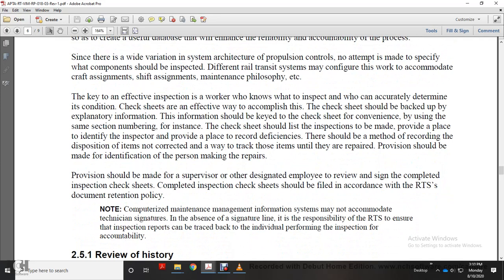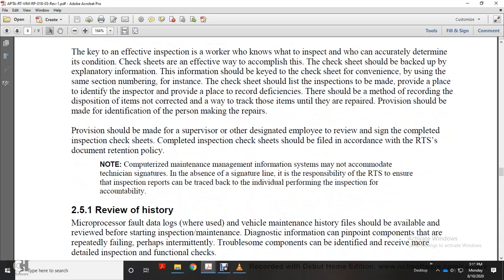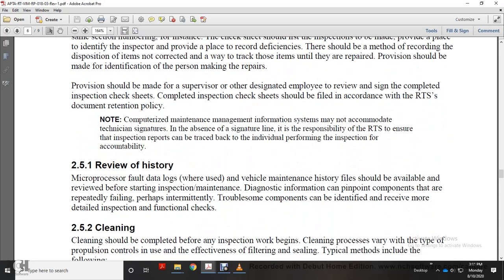The check sheet should be backed up with explanatory information. For convenience, this information should use the same section numbering as the check sheet. The check sheet should list the inspections made, with a place for the identified inspector. There should be a place to record deficiencies, recording the disposition of items not required corrected, and a way to track the items until they are repaired. Provision should be made for identification of the person making the repairs.